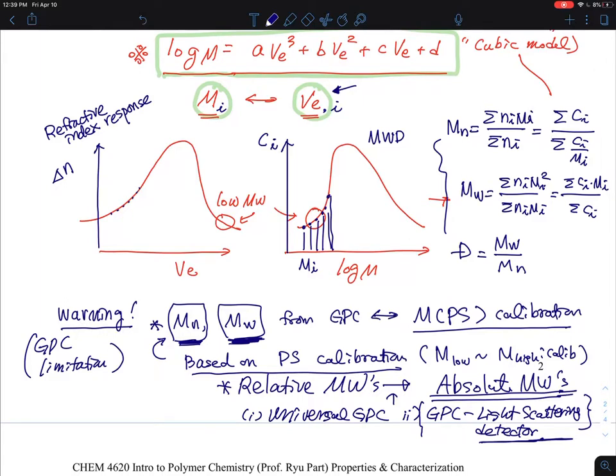So I just want to give you one of the take-home messages is typical method is people do the GPC calibration with monodispersed polymer standard, and then they made a calibration curve, and they do the method that is shown up here to get the average molecular weight of different kinds. And so that's really typically relative molecular weight, most people just say based on polystyrene calibration, and that's all, is sufficient enough for us to have an idea of relative differences in molecular weight using the GPC technique.